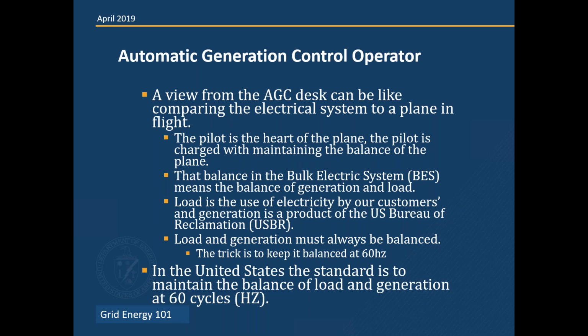In the United States, the standard to maintain that balance of load and generation is at 60 cycles. And I can tell you that load and generation will always be balanced, but the key is to keep it at 60 cycles. If it settles at 58, we're going to damage equipment. Next slide, please.